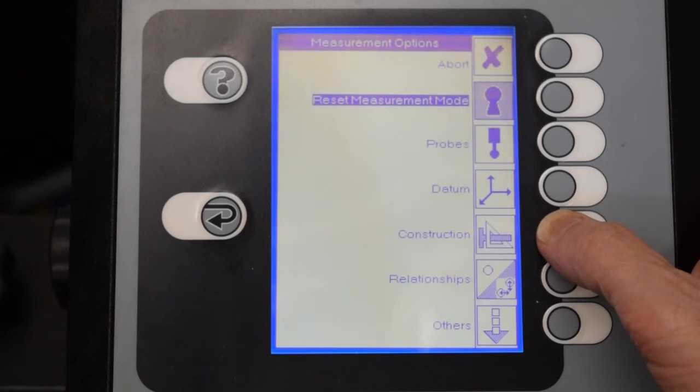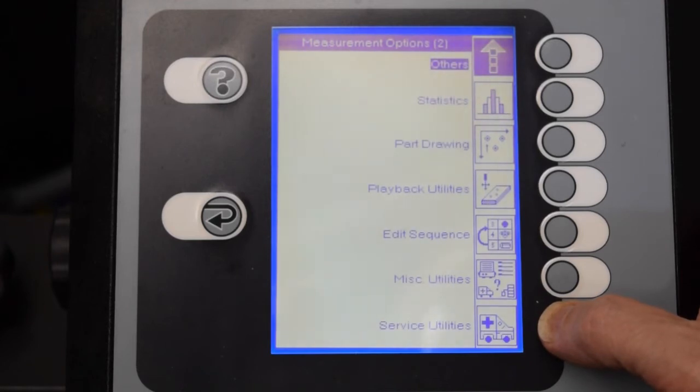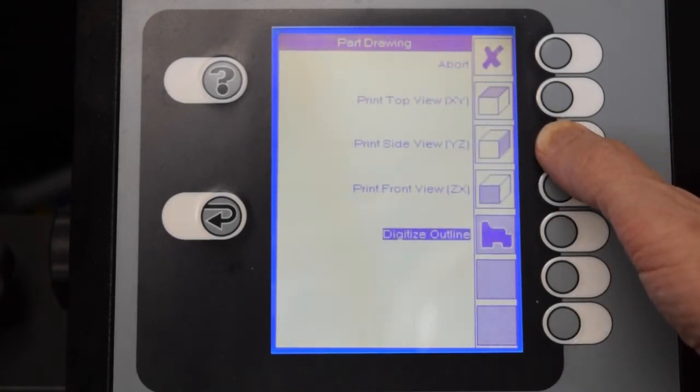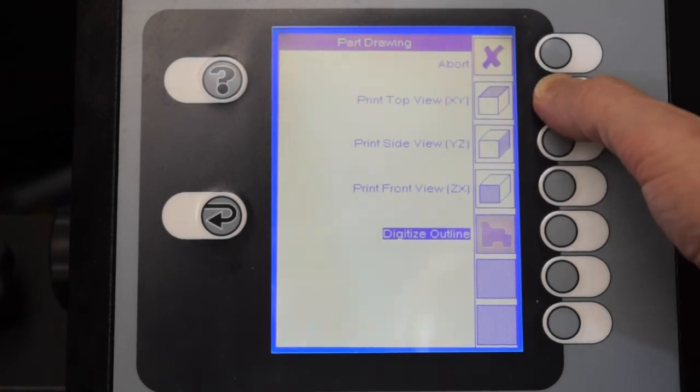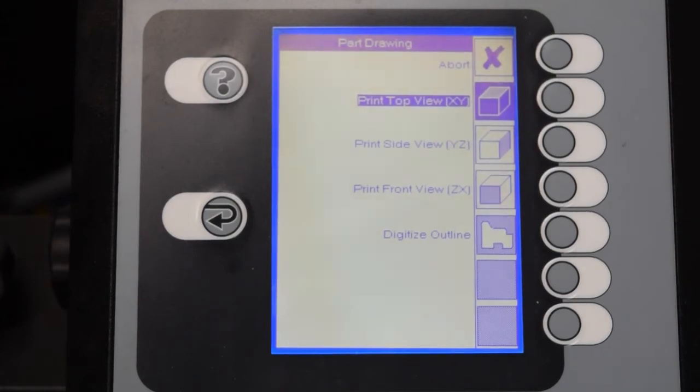At this point, I'm assuming that you've measured all the individual holes, and we can make a printout of the hole drawing with all the holes numbered with the numbers that the CMM was assigned to them. So we start by hitting the tools menu, scrolling down, hitting part drawing, and then pressing print top view.